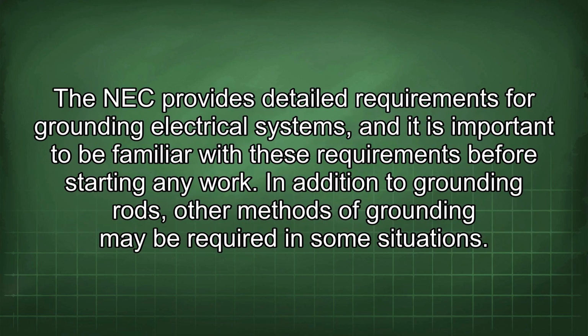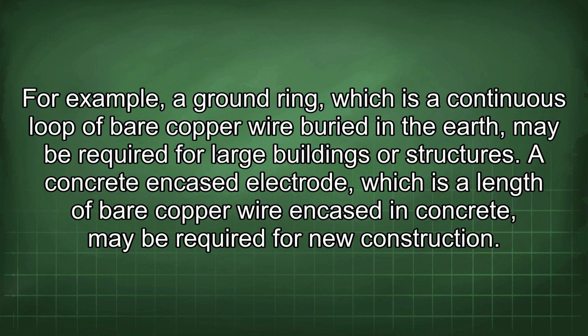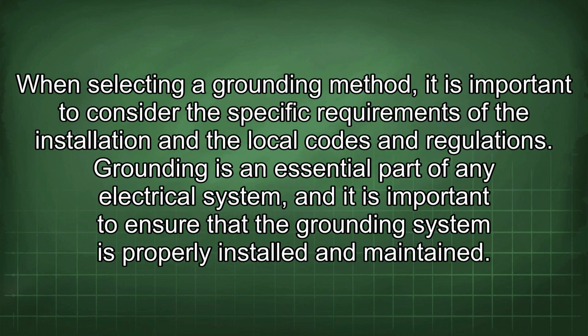When installing grounding rods, it is important to follow all applicable codes and regulations. The NEC provides detailed requirements for grounding electrical systems, and it is important to be familiar with these requirements before starting any work. In addition to grounding rods, other methods of grounding may be required in some situations. For example, a ground ring, which is a continuous loop of bare copper wire buried in the earth, may be required for large buildings or structures. A concrete encased electrode, which is a length of bare copper wire encased in concrete, may be required for new construction.